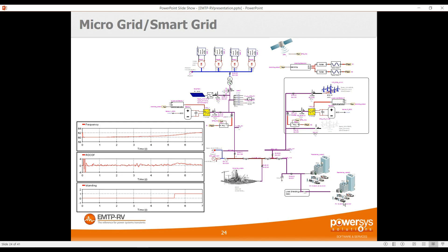Microgrids are another trending study area — for example, islanding detection and islanding mode operation. In this case, we have a network equivalent, disconnect the microgrid from it, and study islanding detection by monitoring the variation of frequency and rate of change of frequency. The microgrid includes diesel generators, a wind park, batteries, inverters, and PMUs that communicate using GPS time for islanding detection — a very advanced study of microgrid and smart grid behavior.